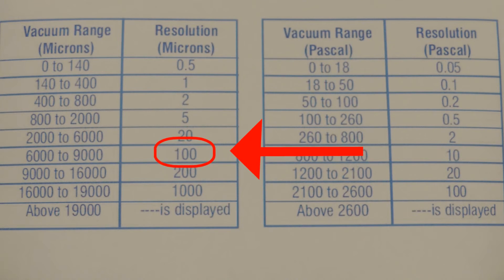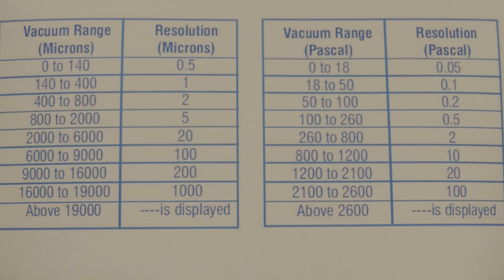In that 6000 to 9000 range, the display reading will change in 100 micron increments. This keeps the display from being a blur of numbers.